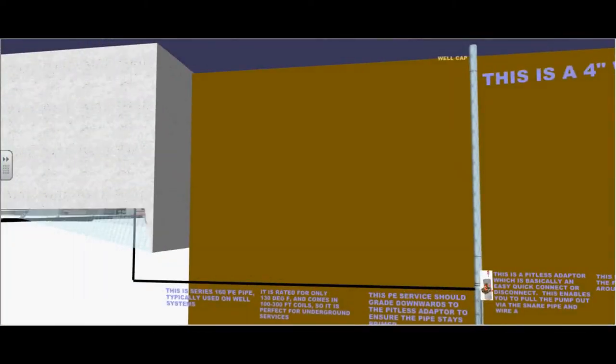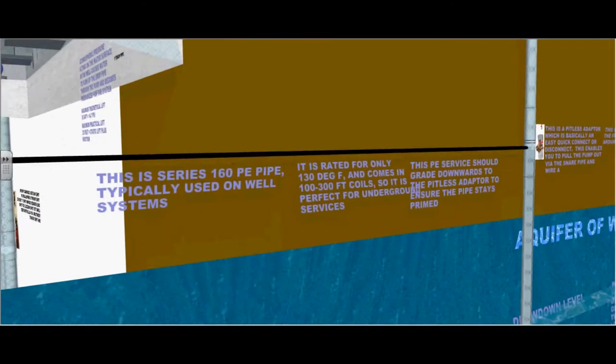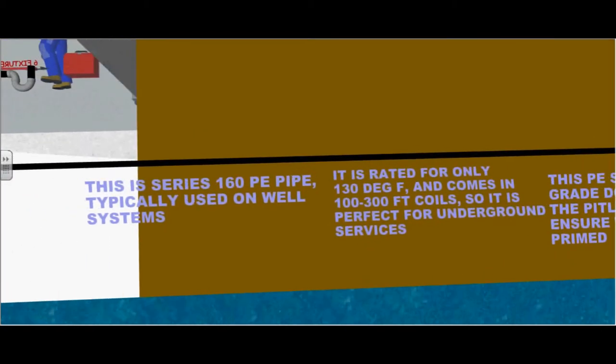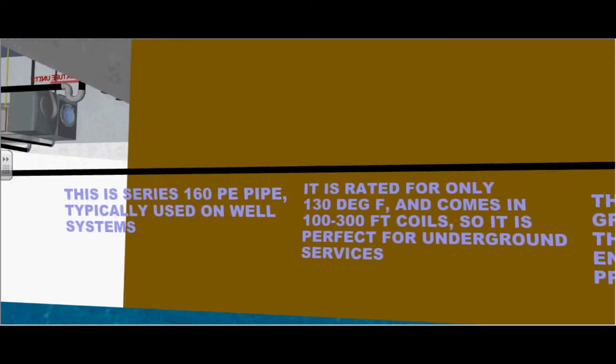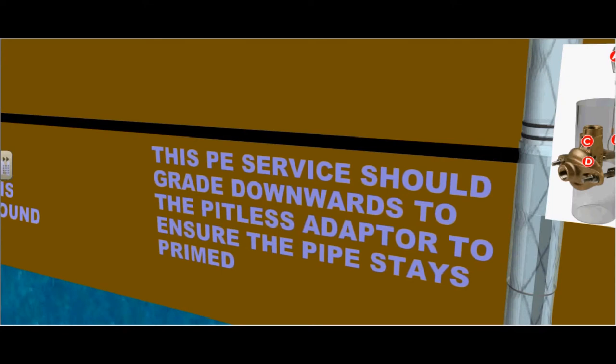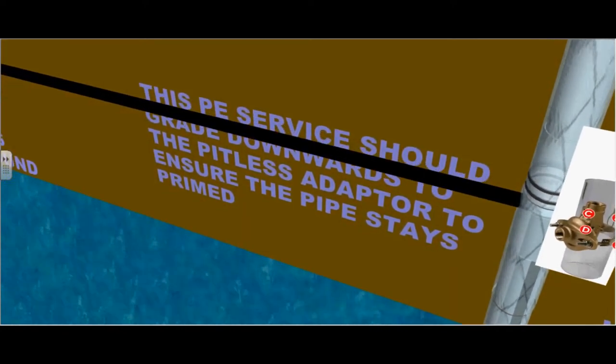This is a series 160 polyethylene pipe typically used on well systems. It is rated for only 130 degrees Fahrenheit and comes in 100 to 300 foot coils, so it is perfect for underground services. This polyethylene service should grade downwards towards the pitless adapter to ensure that the pipe stays primed.